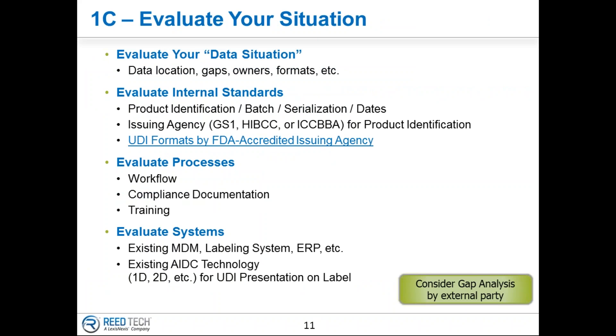After you figure out the requirements for your inventory, next would be to evaluate where you are — this is commonly referred to as a gap analysis. Look at where your data is residing. Are you currently identifying it in one of the FDA-approved agencies, like GS1, HIBCC, or an ICCBBA standard? If not, you need to contact one of those three, set up an account, and start understanding their protocol for numbering.